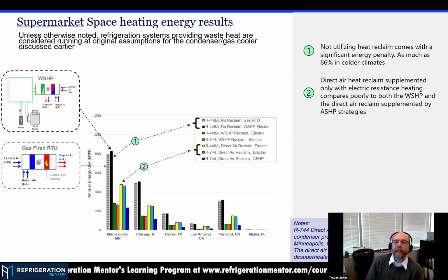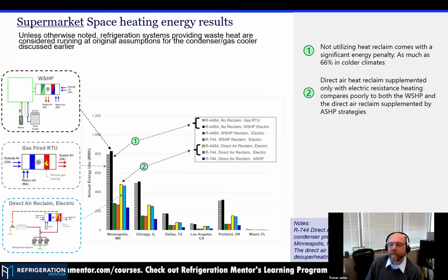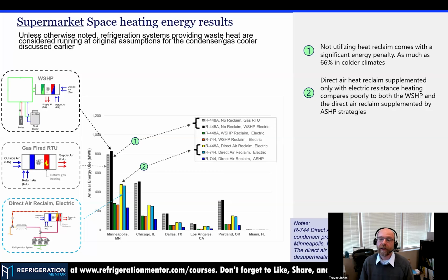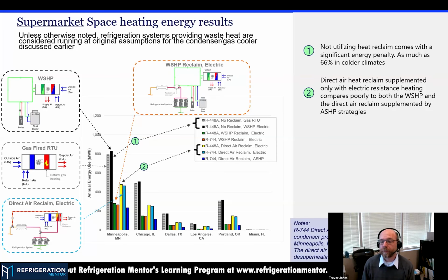Now, when we start looking at reclaim in the supermarket, the direct air reclaim doesn't do quite as well as the water source heat pump. A lot of that had to do with the fact that this is looking at both heating and refrigeration energy, so it's a total of the refrigeration and heating energy layered together. If we're spending a lot of additional energy on auxiliary heat, which we don't necessarily need to do, or a lot more on refrigeration, then it's going to show up in the total. So the water source heat pump, especially on the supermarket where we're closer to parity with our loads, needs a lot less auxiliary heat, is what we found.